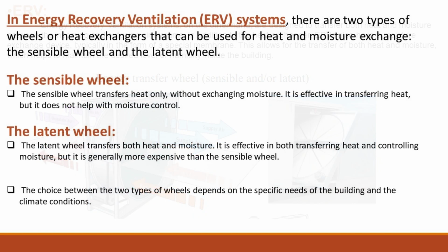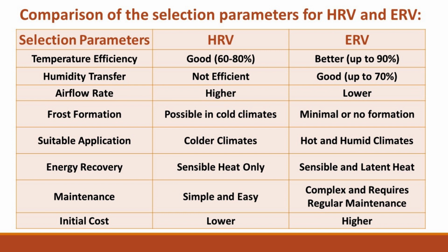the building. In energy recovery ventilation, ERV systems, there are two types of wheels or heat exchangers that can be used for heat and moisture exchange: the sensible wheel and the latent wheel. The sensible wheel. The sensible wheel transfers heat only, without exchanging moisture. It is effective in transferring heat, but it does not help with moisture control. The latent wheel. The latent wheel transfers both heat and moisture. It is effective in both transferring heat and controlling moisture, but it is generally more expensive than the sensible wheel. The choice between the two types of wheels depends on the specific needs of the building and the climate conditions. Here is the comparison of the selection parameters for HRV and ERV.